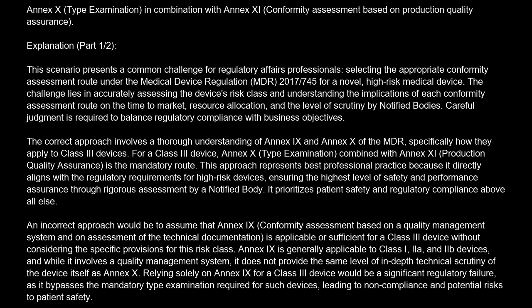The challenge lies in accurately assessing the device's risk class and understanding the implications of each conformity assessment route on the time to market, resource allocation, and the level of scrutiny by notified bodies. Careful judgment is required to balance regulatory compliance with business objectives. The correct approach involves a thorough understanding of Annex IX and Annex X of the MDR, specifically how they apply to Class III devices.